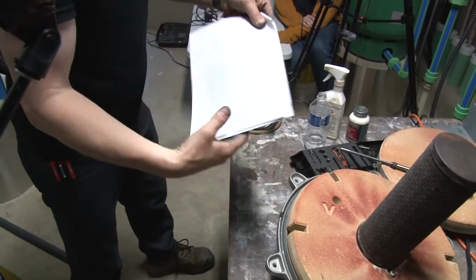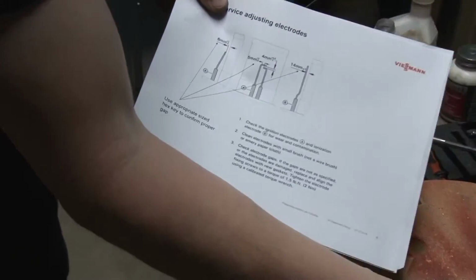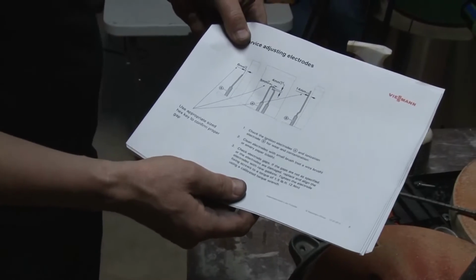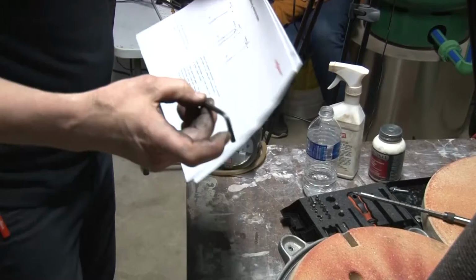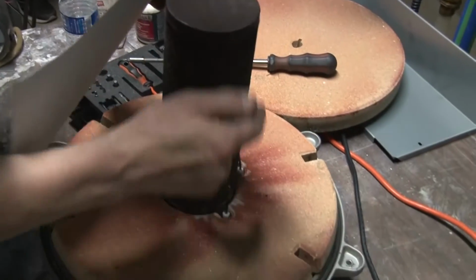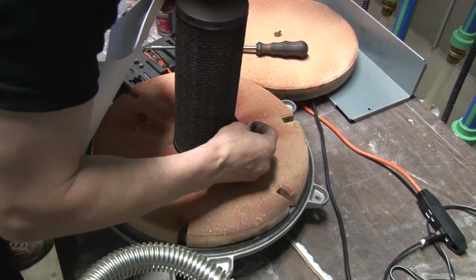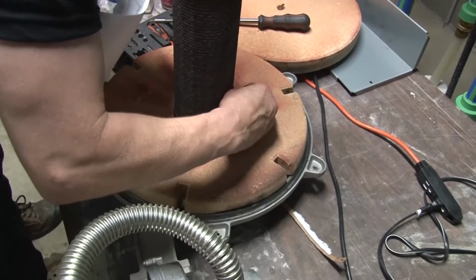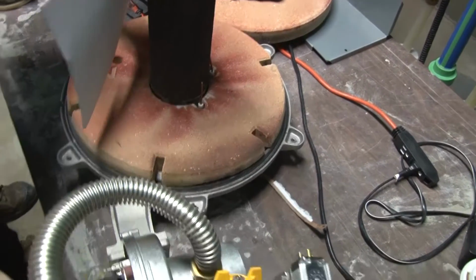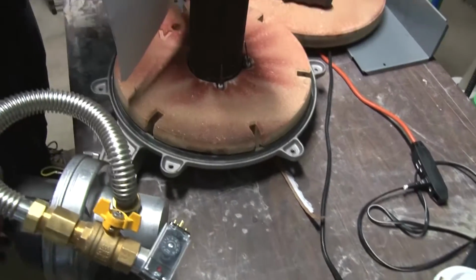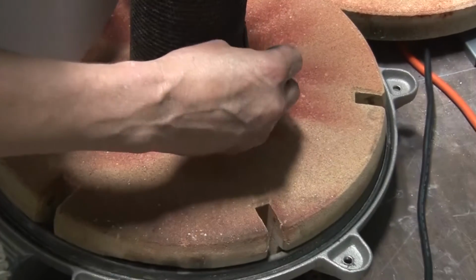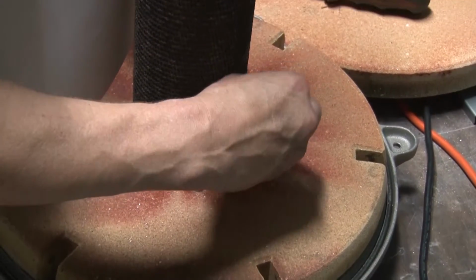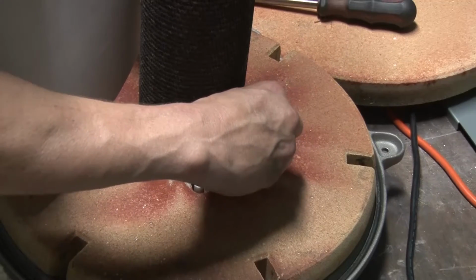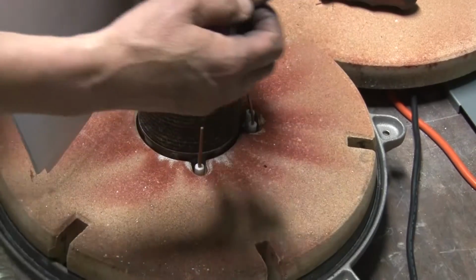So when we're measuring the gaps, what I'm talking about here is the distance of the electrodes from the burner mesh. And 6 millimeters, I would have a 6 millimeter Allen key. And if I slid that basically between the burner mesh and that electrode right there, I'm going to angle this for you a little bit so you can see a little better maybe. That's going to slide in there, and there's a tolerance. So this one here is a little bit bigger, but just get the idea. That gives me my gap.